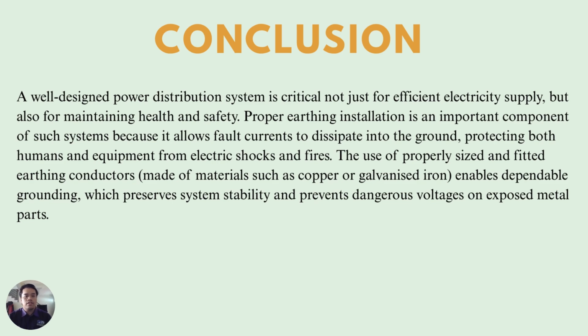The conclusion for this presentation is that a well-designed power distribution system is critical not just for efficient electricity supply but also for maintaining health and safety. Proper earthing installation is an important component of such systems because it allows fault currents to dissipate into the ground, protecting both humans and equipment from electric shock and fires. The use of properly sized and fitted earthing conductors, made of materials such as copper or galvanized iron, enables dependable grounding, which preserves system stability and prevents dangerous voltage on exposed metal parts.